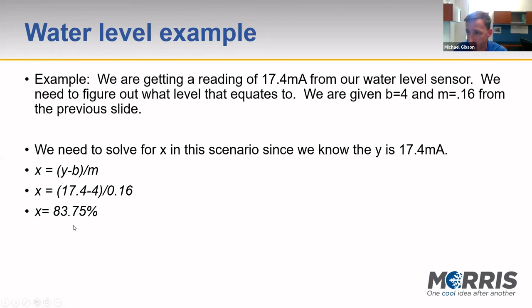We know that the water level sensor can read between 0 feet and 6 feet. So it's basically a simple proportion to figure out what the water level actually is. 6 feet is 100%, and we have X is equal to 83.75%. After we do that simple proportion, we figure out that the water at 83.75% is 5.025 feet.